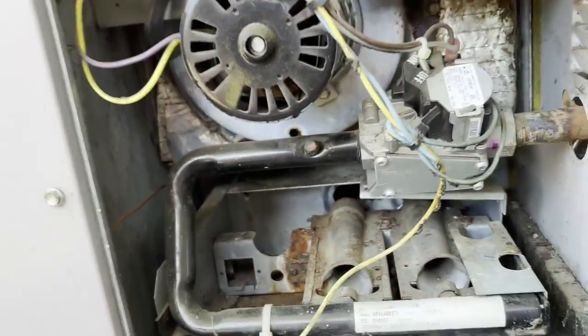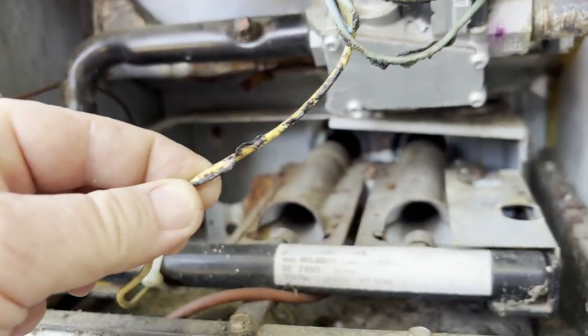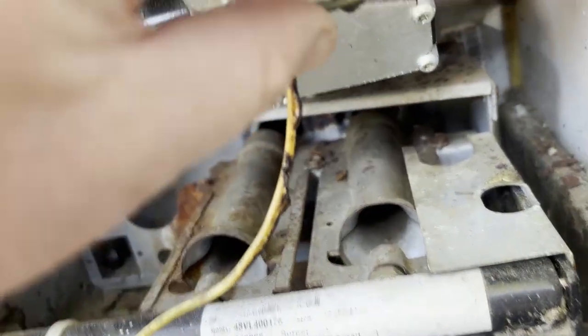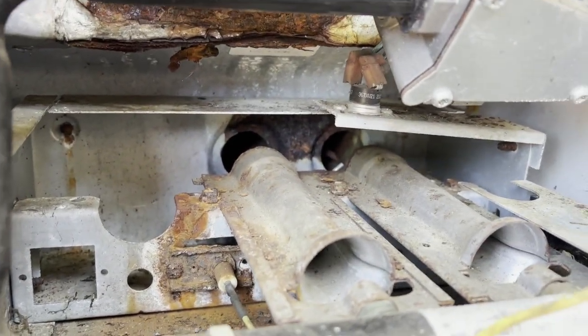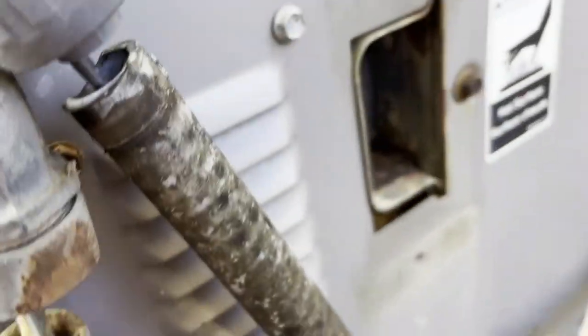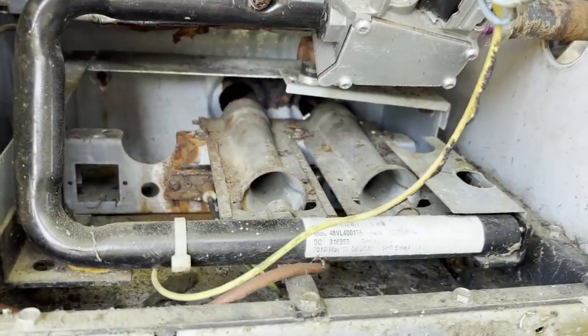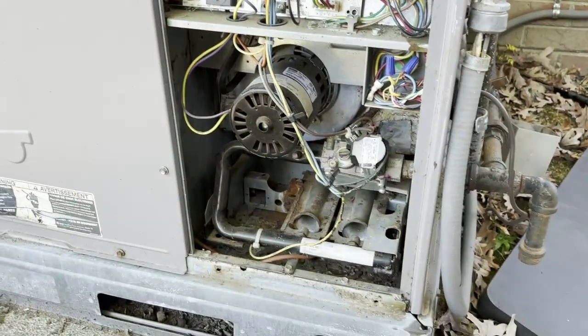Flame rolling out in there. It's been going out, and it would work, but it wouldn't work. You notice these wires right here, see how badly those are melted? So we've been getting flame rollout in this thing. I'm gonna guess when I get this apart we're gonna find a cracked heat exchanger, because I've already checked all my blades, I took it off, it was on there, but all those blades are on the wheel, so I'm guessing we're gonna find a heat exchanger wide open.